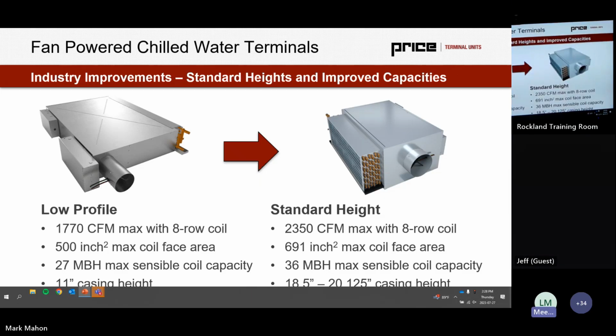So I like to talk a little bit about the history of this product because I think it's interesting. It came from the DMV area, so DC, Maryland, Virginia. And the rationale for it, or the reason why it originally came up, was because the Pentagon was doing a retrofit, and being a historic building with low plenums, not being allowed to be built very tall because of all the other historical buildings in the area, they needed something that could fit in a foot of plenum height, but that could provide like a LEED high level certification as far as energy efficiency went.